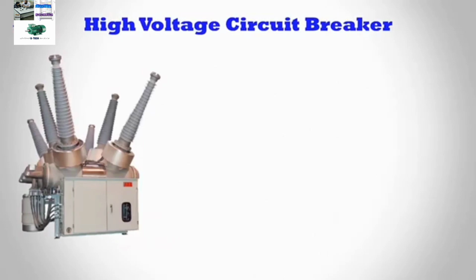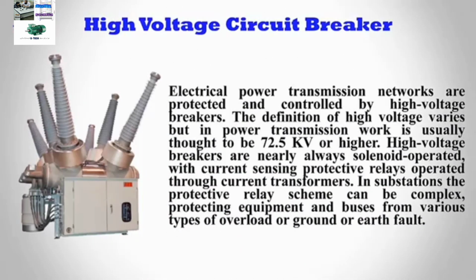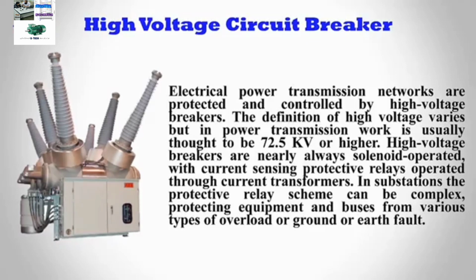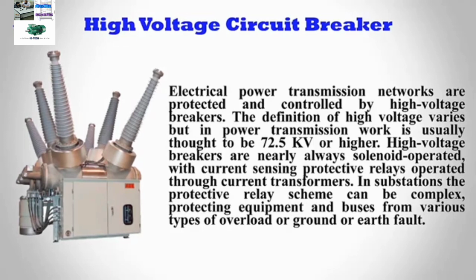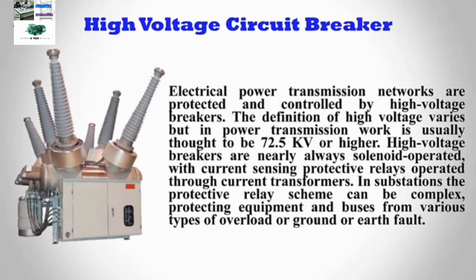Electrical power transmission networks are protected and controlled by high voltage breakers. The definition of high voltage varies, but in power transmission work it is usually thought to be 72.5 kV or higher. High voltage breakers are nearly always solenoid operated, with current sensing protective relays operated through current transformers. In a substation, the protective relay scheme can be complex, protecting equipment and buses from various types of overload or ground or earth fault.